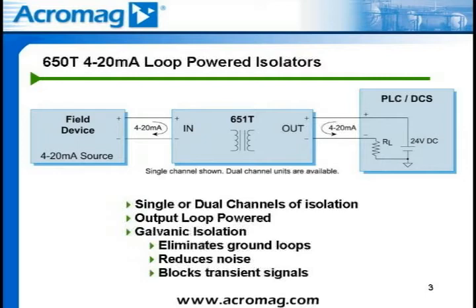Galvanic isolation is provided in the 651T, 652T, and 653T from input to output, and also from channel to channel in the 652T and 653T. This galvanic isolation eliminates potential ground loops. Transient voltage suppression protects equipment from high voltage surges and spikes, and input filtering circuitry reduces noise effects on the analog signal.